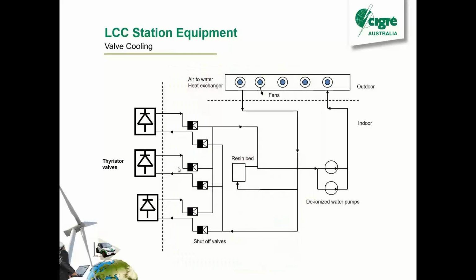Valve cooling. The thyristors are pretty low loss, but they do get hot. And when you're sending 1,000 megawatts, the amount of heat that you've got to dissipate is not insubstantial. So they're generally water cooled. The thyristors are sandwiched between heat sinks, and the heat sinks actually conduct the line current most of the time as well.